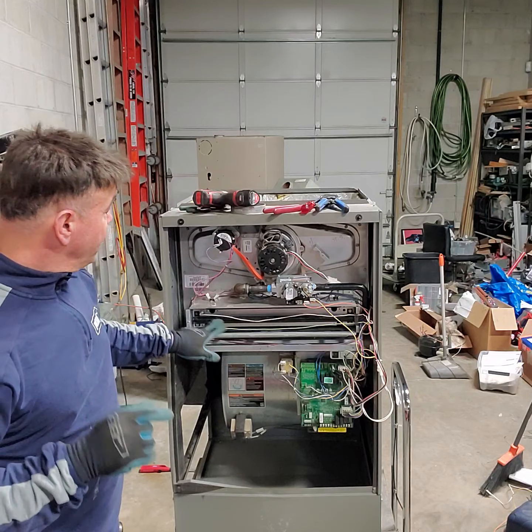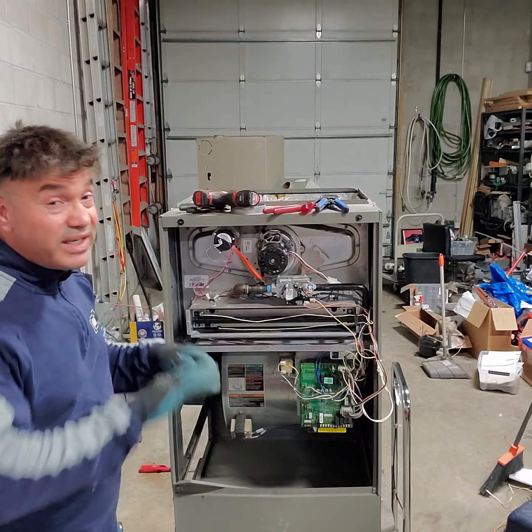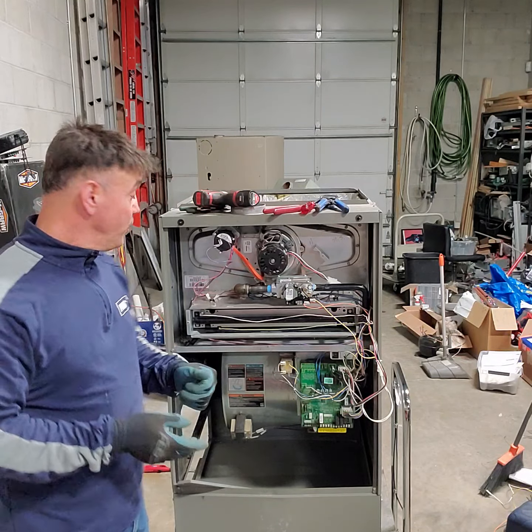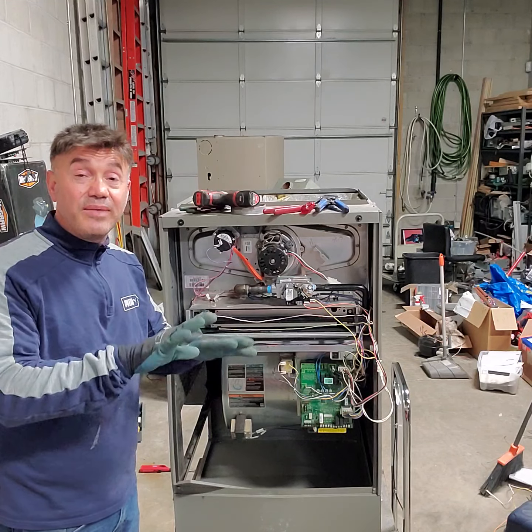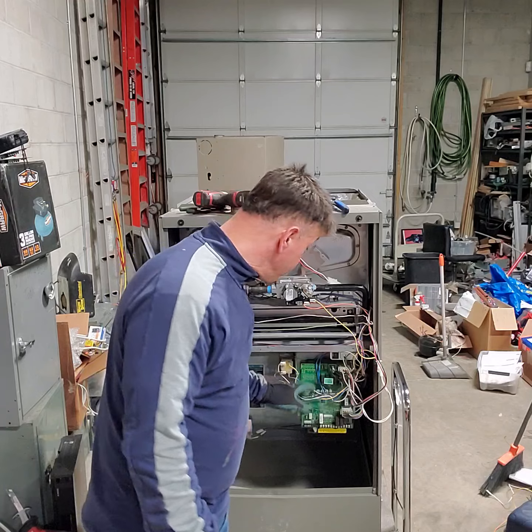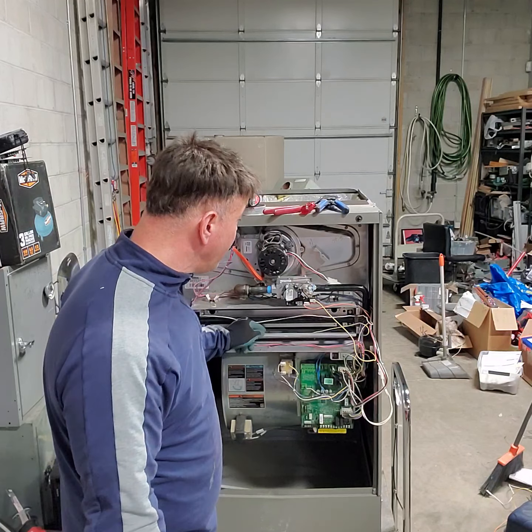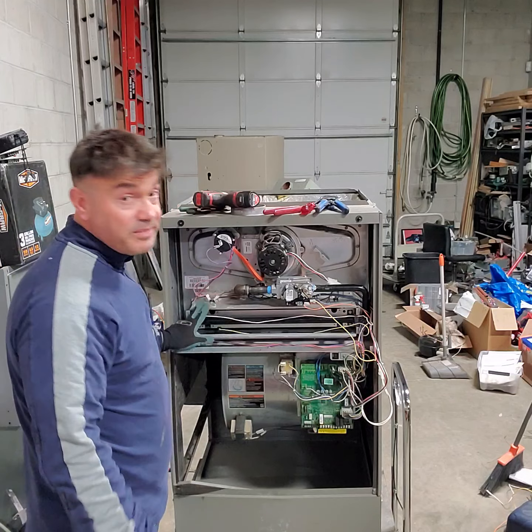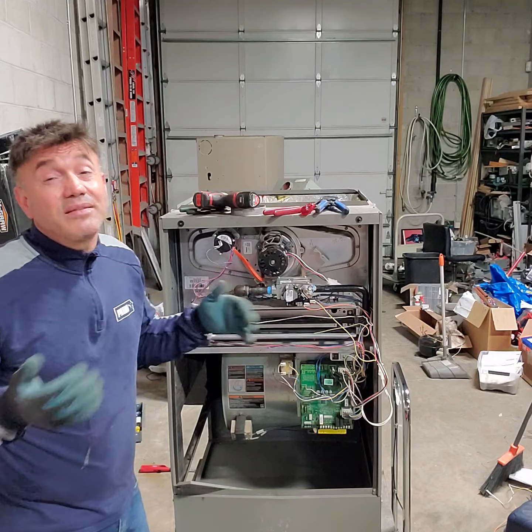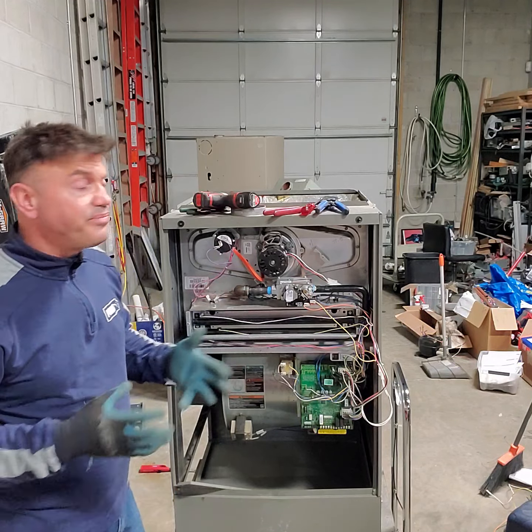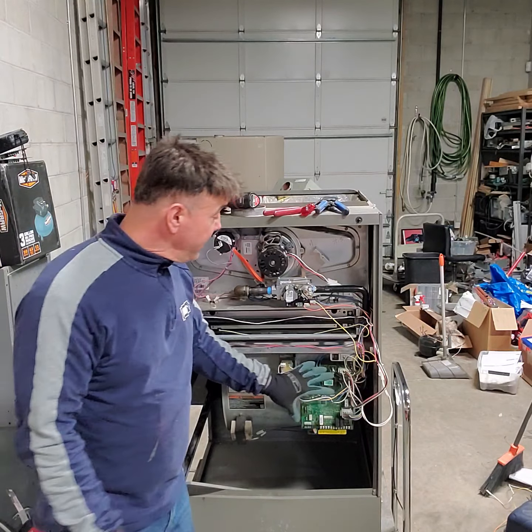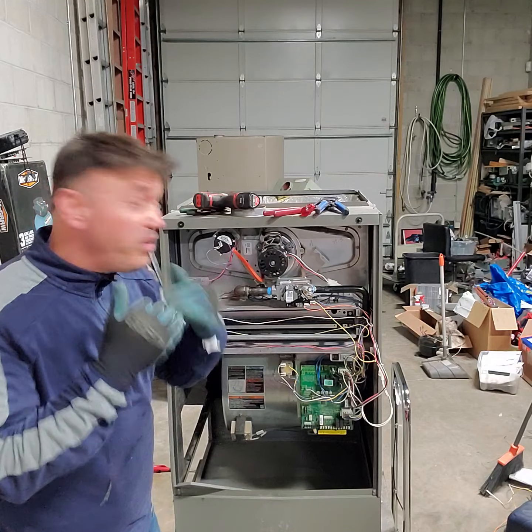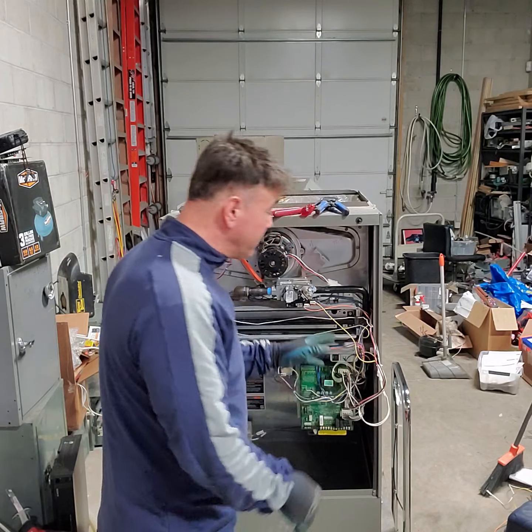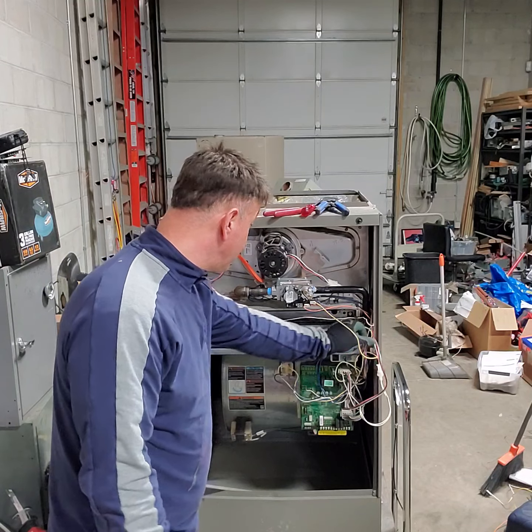Again, it's not expensive. Other thing: when this happens, you clean it and it's still doing the same, and then you put a brand new one and it's still doing the same. The fire comes on, 5 seconds, stop. Now you have a ground problem, so you check for grounds. If you don't have a ground to the chassis of the furnace, the flame sensor will do the same thing. A lot of people I have seen change parts. I have a customer, an engineer, but he didn't understand the thing. He replaced the control board and gas valve, and what it was, the ground wire was disconnected. So you have to make sure all the grounds are in place.